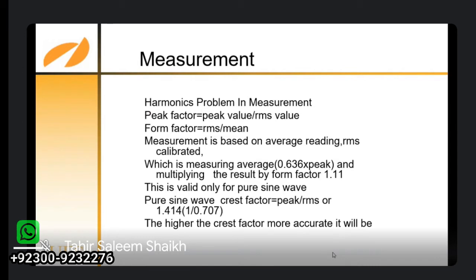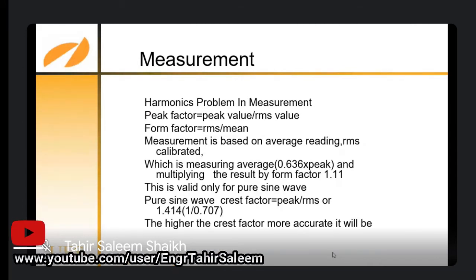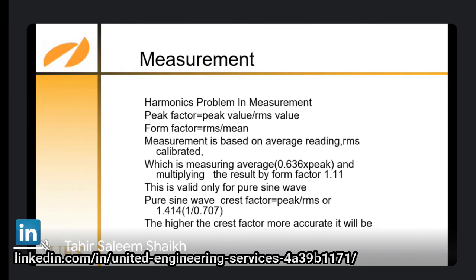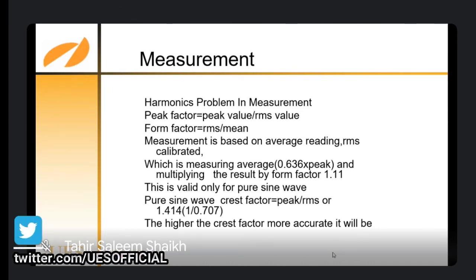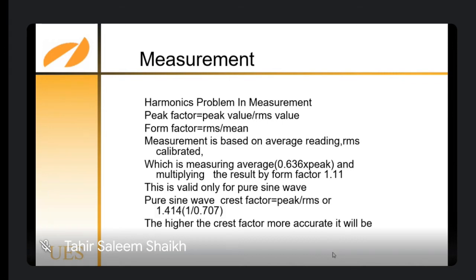Harmonic problems and measurement: peak factor, peak value, form factor. Measurement is based on average reading, RMS calibrated, which measures the average 0.636 times the peak and multiplies the result by a form factor of 1.11. This is valid only for a pure sine wave. For a pure sine wave, the crest factor would be peak 1.414 upon 0.707. The higher the crest factor, the more accurate it will be.